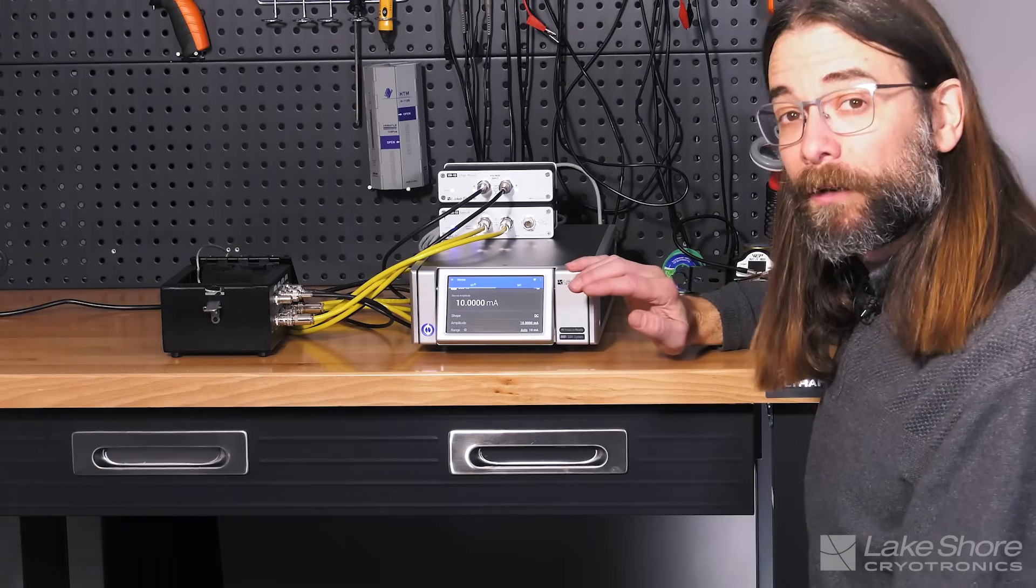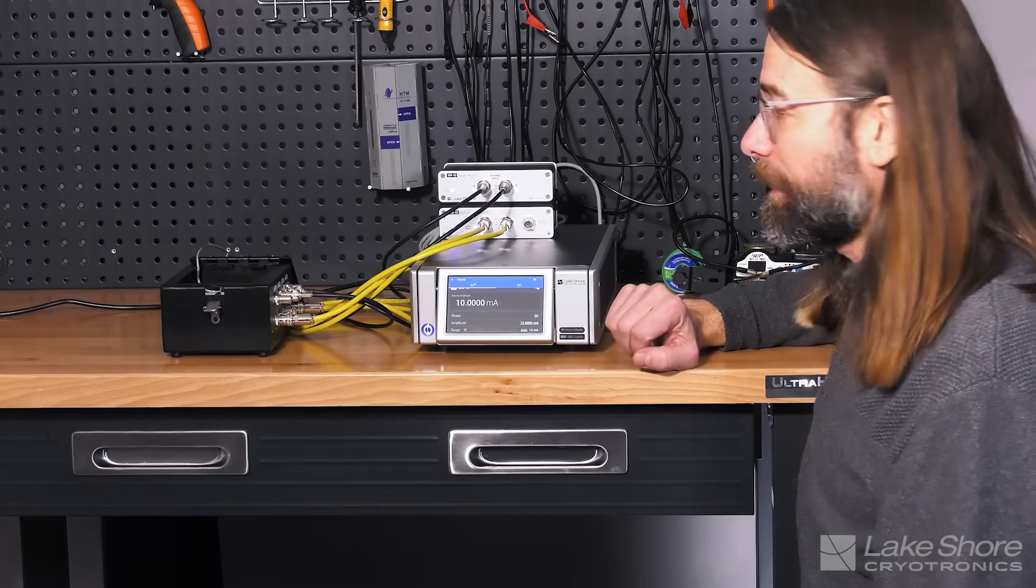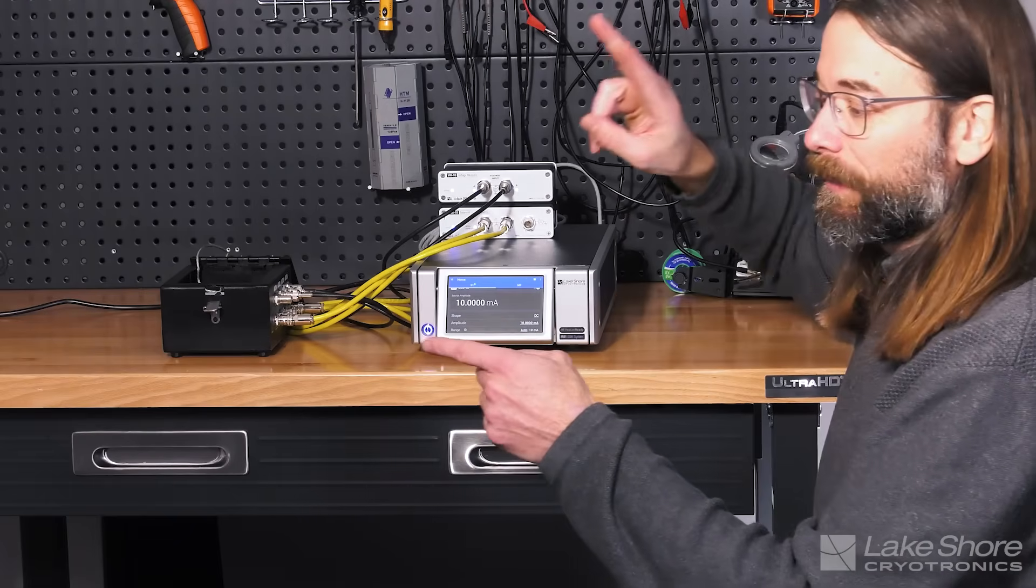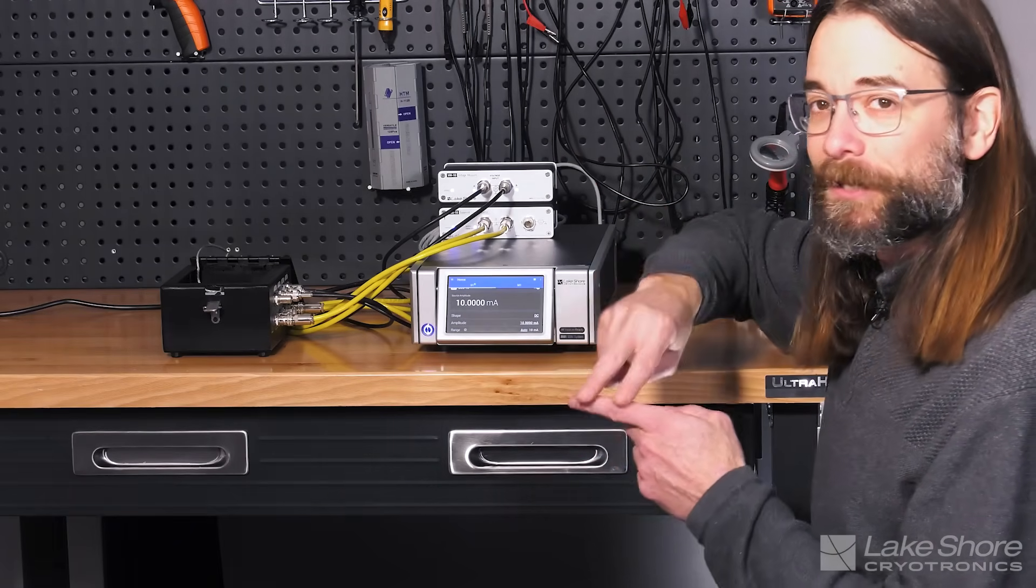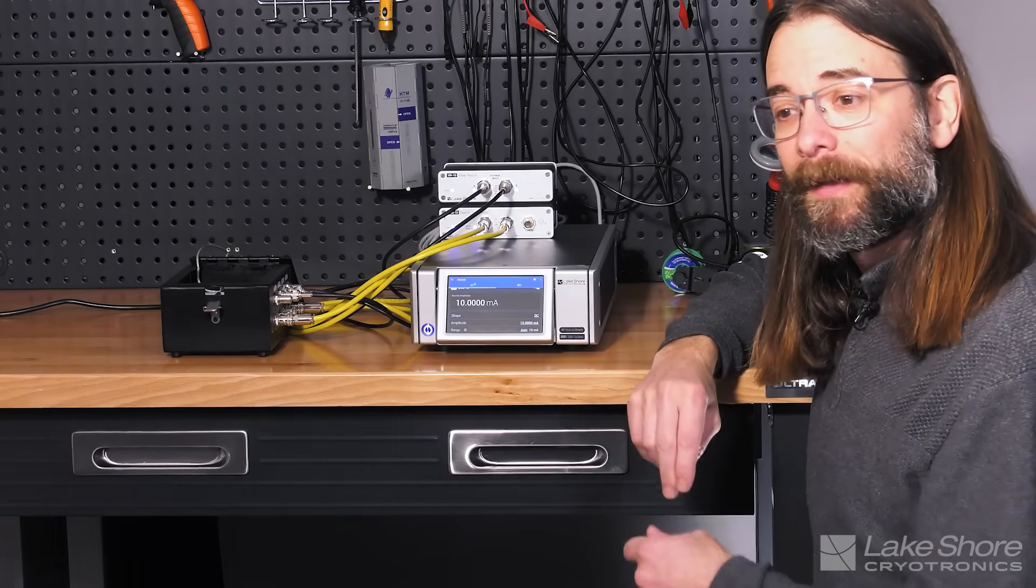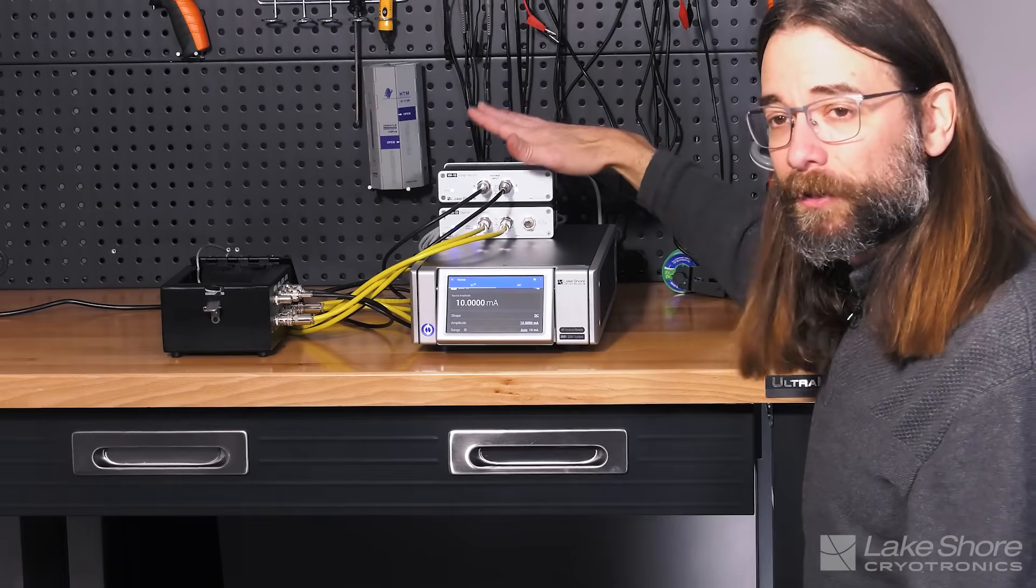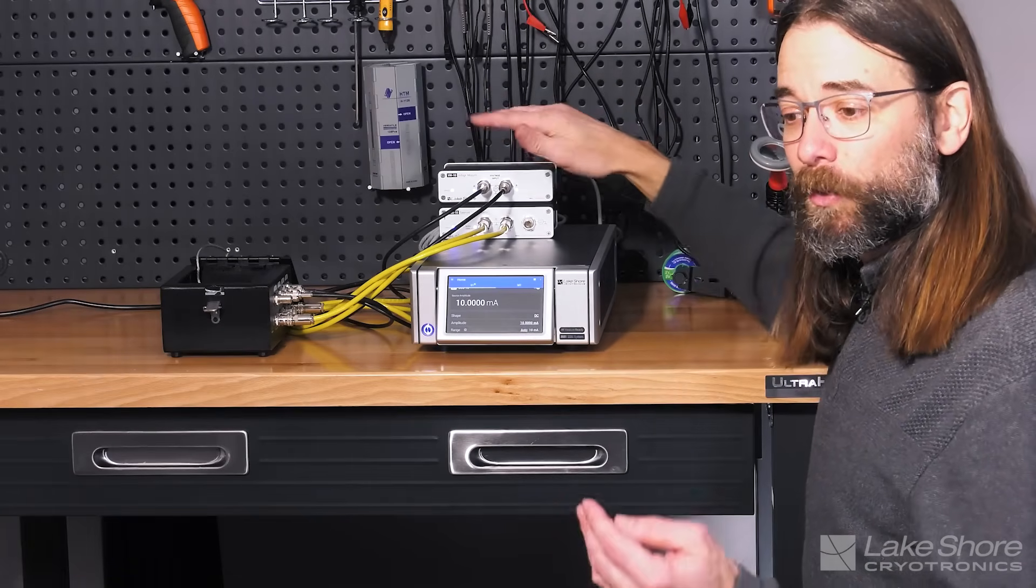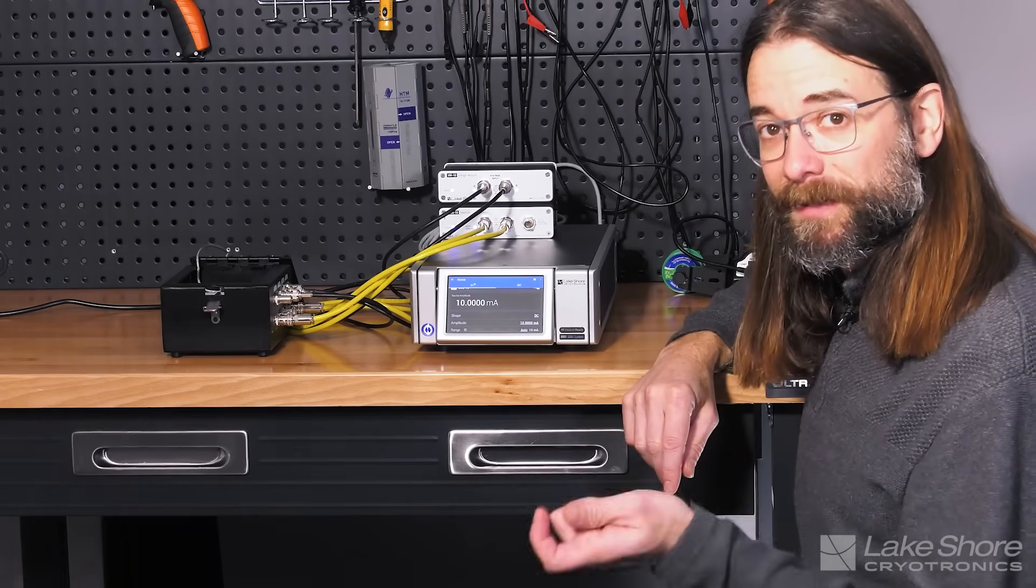This technique is called a four-wire or Kelvin measurement. And in that setup, we're sourcing current, but then we're making a remote voltage measurement on the device under test itself. And in that way, since there's very little current flow to the voltmeter, we're going to have a more accurate measurement of the resistance that we're testing.